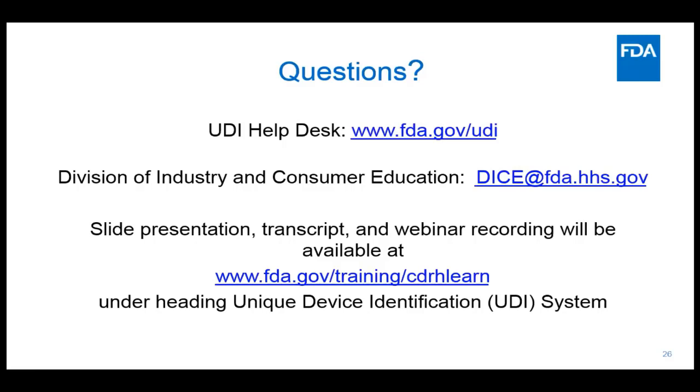Next we have Eric Carey. Your line is open. Hi, I have a question. I have a first aid kit with, let's just say, Band-Aid, gauze pads, and non-latex gloves. If I was to now add aspirin to that kit, what would my UDI requirements be? Well, that would be a combination product, and that is outside the scope of this particular guidance document, and that's the purpose of this webinar. If you'd like to know what the UDI requirements are for combination products, I suggest you submit that to the help desk, and we can respond to that question there.